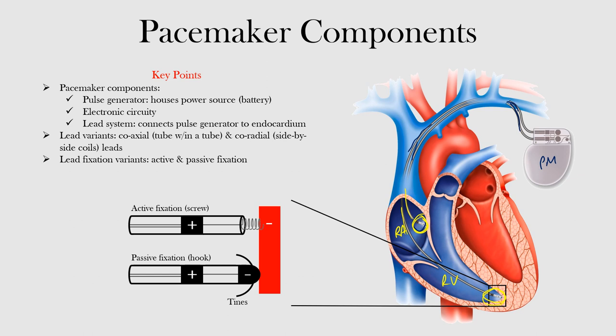Here we can see active fixation and passive fixation. In this blown-up image, the red area represents the myocardium. In the active form, you have the anode and cathode, and the active lead essentially screws or inserts itself directly into the myocardium for stability. In passive fixation, there are tines that act like hooks, interfacing with the myocardium but not actually inserted into it. These inner tines anchor the leads in passive fixation.